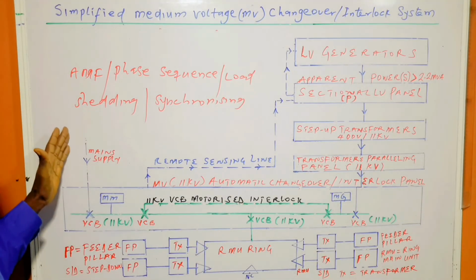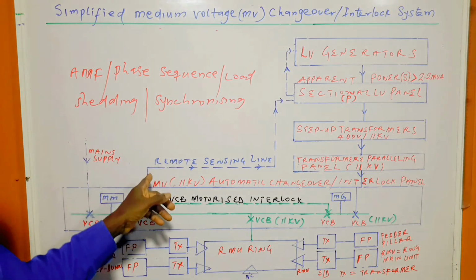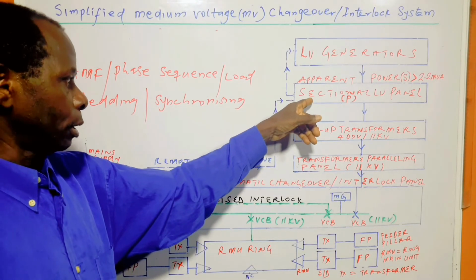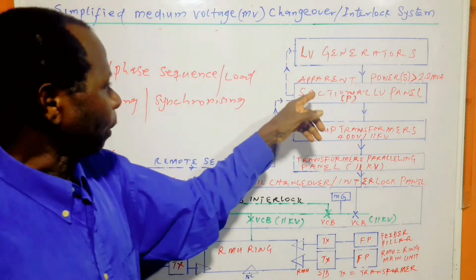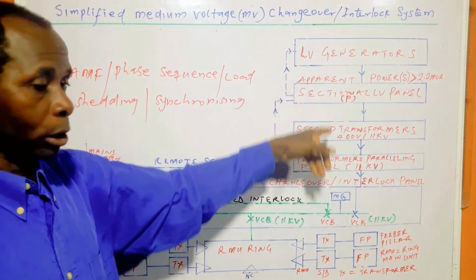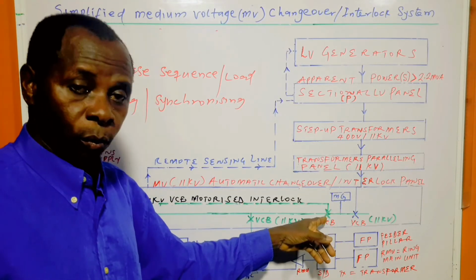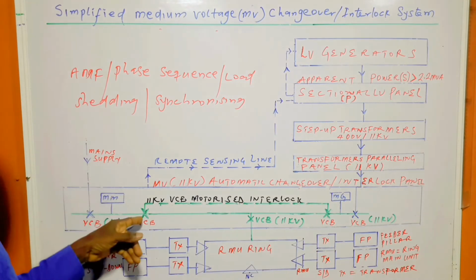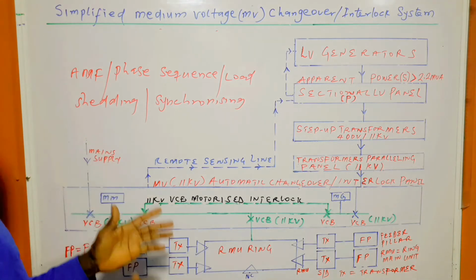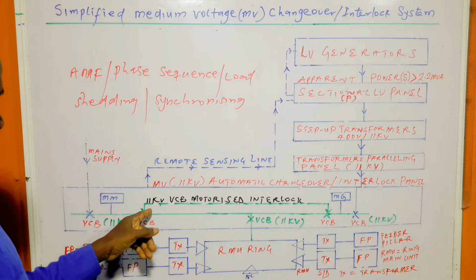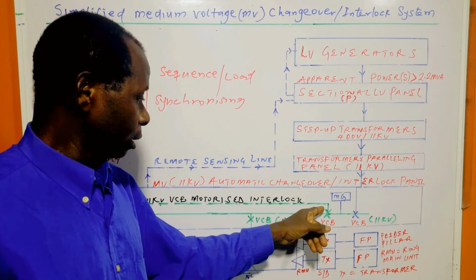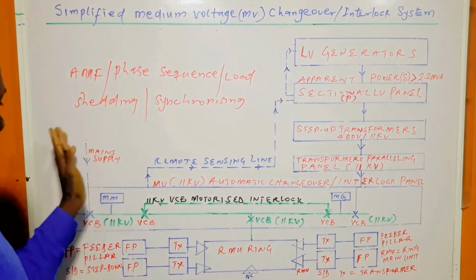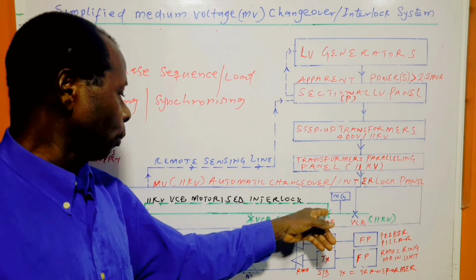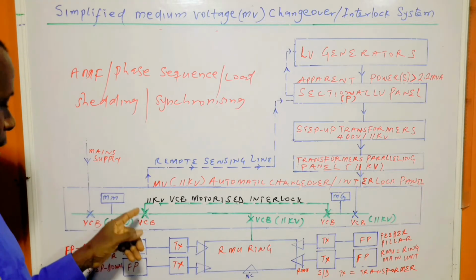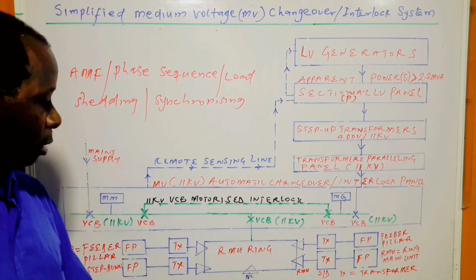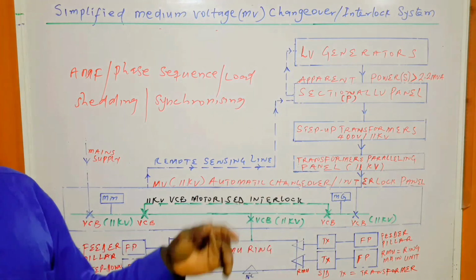Now when the power is restored, that is, the voltage is restored from the mains, this remote sensing line reports to panel P, and panel P signals the generators to shut down, and simultaneously this circuit breaker will open and the mains circuit breaker will close. So one at a time. Before, this one was open, and when the generators were working, this one was closed. Now that the mains voltage is restored, this one will open, and the mains side of the interlock will close. And this is the common bus section, delivering voltage to the load.